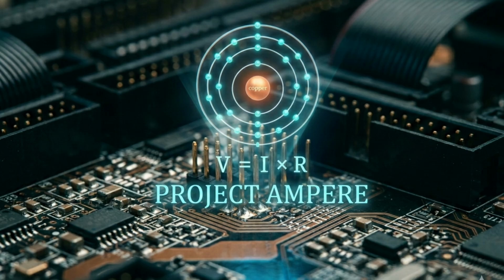We have talked extensively about controlling the power. Now let's talk about saving the system when things inevitably go wrong. The guardians of the bus. Circuit breakers and fuses. There is a golden rule here that I think surprises a lot of people who are outside the aerospace industry. The circuit breaker does not exist to protect the device. Say that again for everyone listening. It is the single most misunderstood concept in electronics. The circuit breaker exists solely to protect the wire.